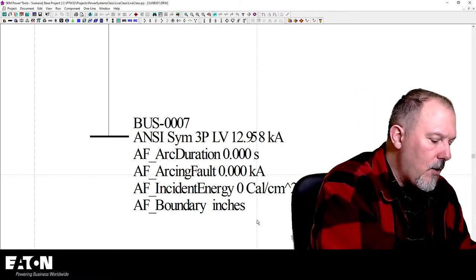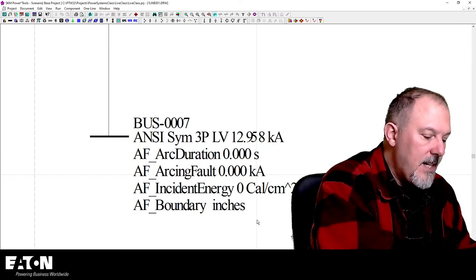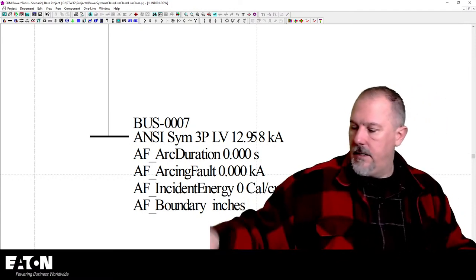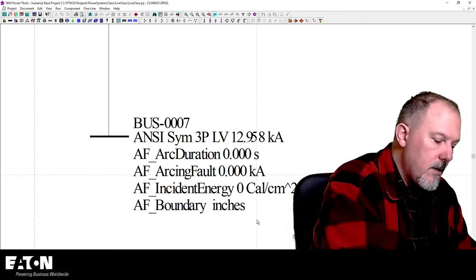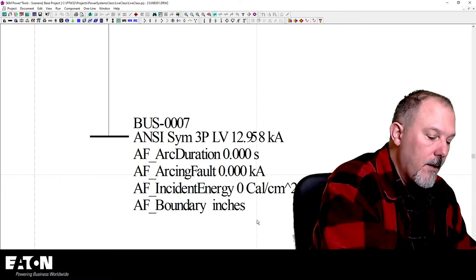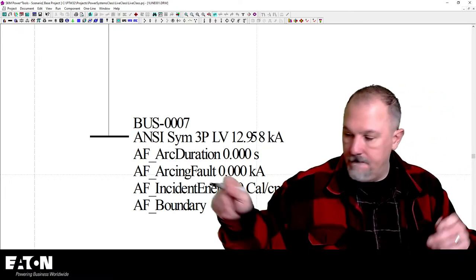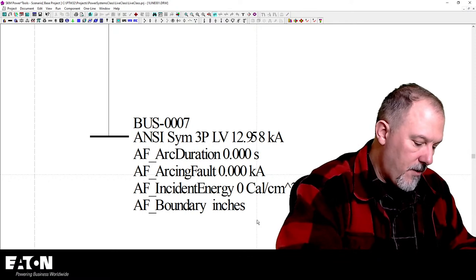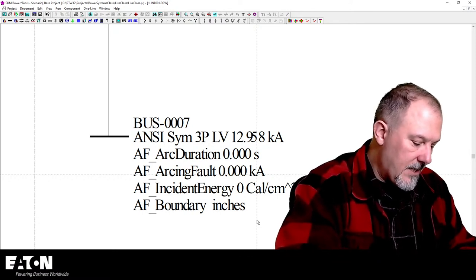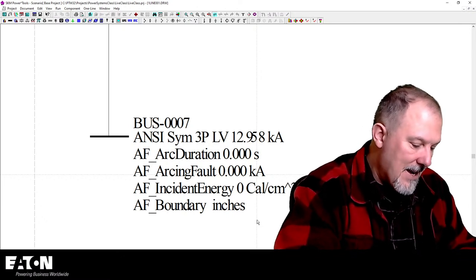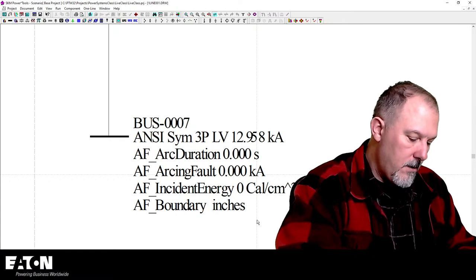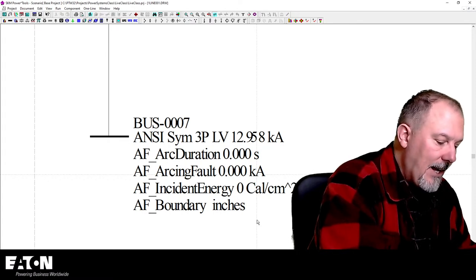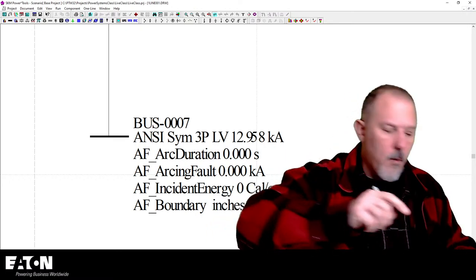0.15 times 1500 divided by 300. And then I have to do 460 squared divided by 480 squared. Okay, calculator: 0.15, 1500 times 300 divide, 460 squared times 480 squared divide, 0.6888. And the angle, the X to R of that motor, was 4.9.